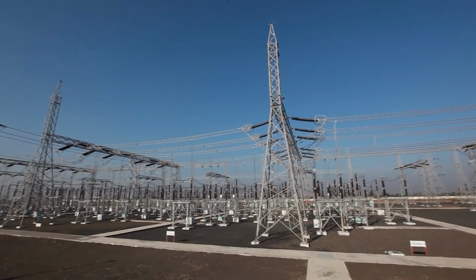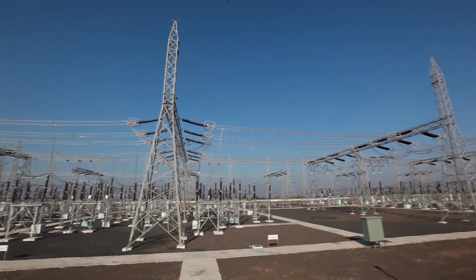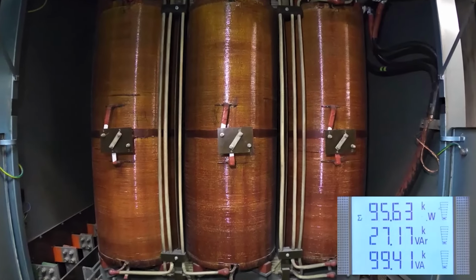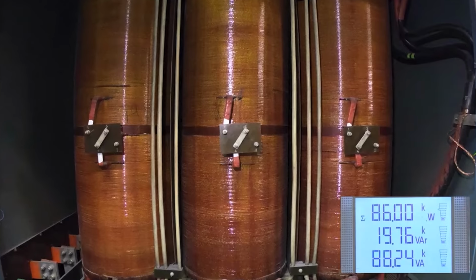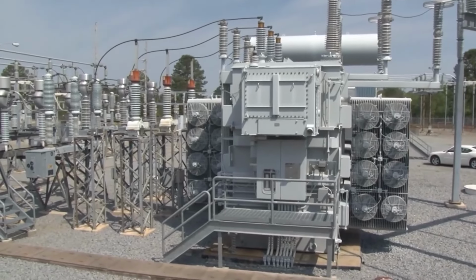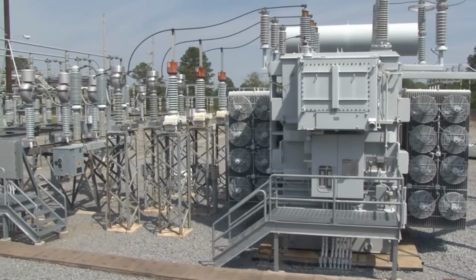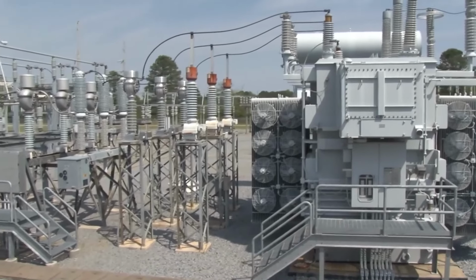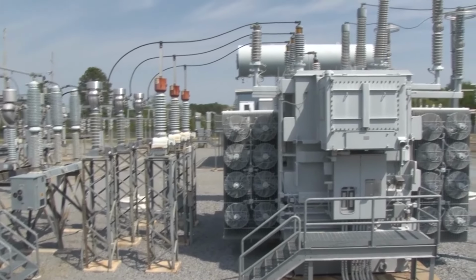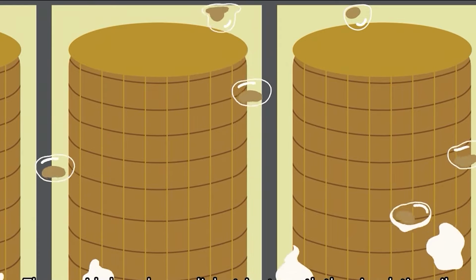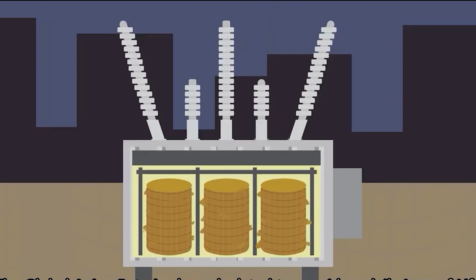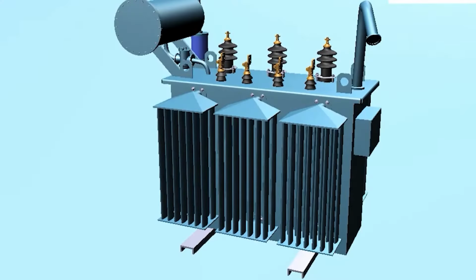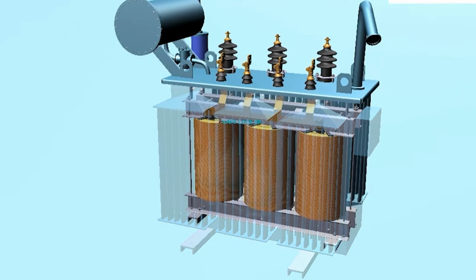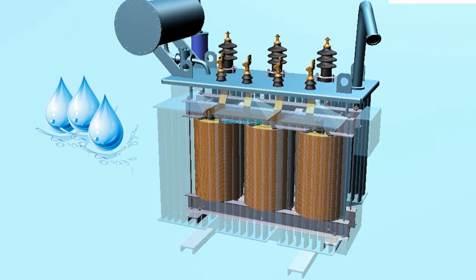We have already said in our past videos that insulation is one of the most vulnerable places of a transformer, and in fact the lifetime of a transformer is determined by the service life of its paper-made insulation. In turn, the service life of paper insulation is greatly influenced by water, which contributes to the destruction of cellulose molecules and a decrease in electrical strength. Therefore, throughout the entire life cycle of the transformer, water from the winding insulation must be periodically removed.